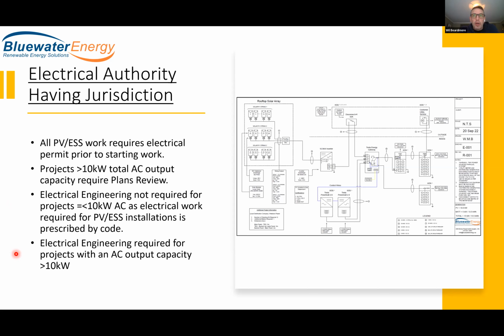That applies if we're applying for a connection impact assessment, and I'm going to get into that in a minute. So here's what a design for plans review is going to look like. We're going to show the PV modules. We're going to have all the technical information in terms of electrical output from each module, right up to the string level into the inverter. We're going to show where the connections are happening, the overcurrent protection devices, what the point of connection is, and the conductor sizing. These are all the things that are required on the ESA plans review submission.